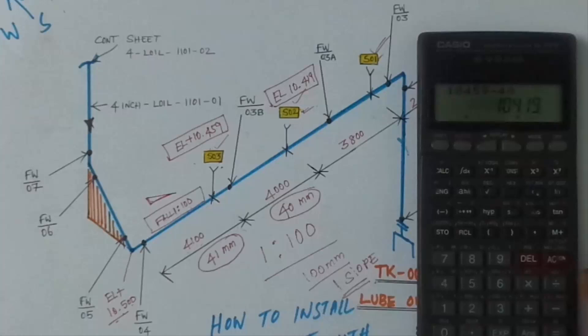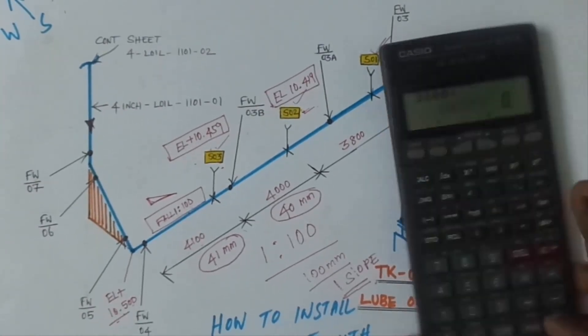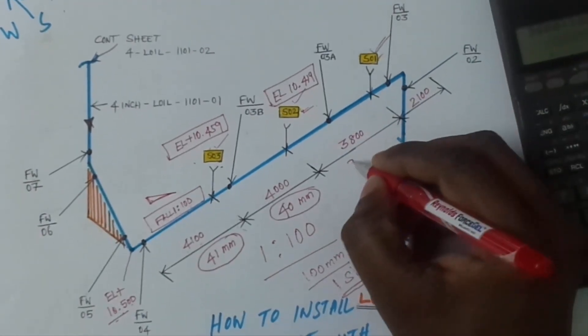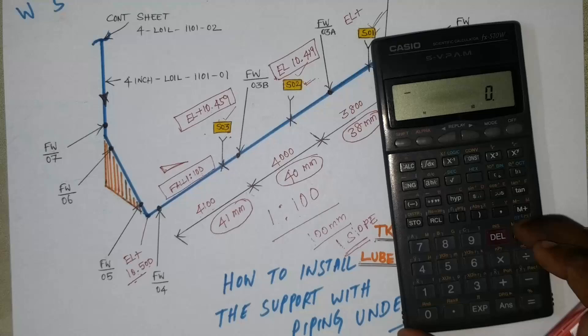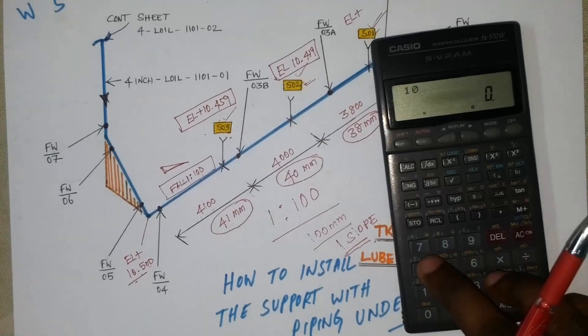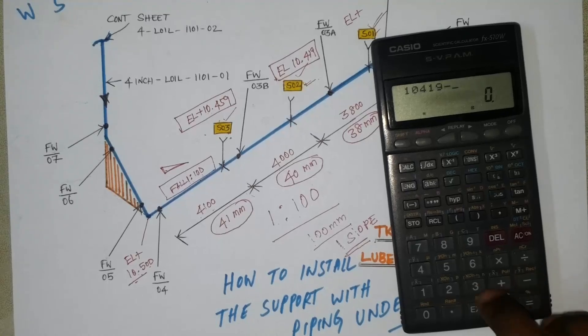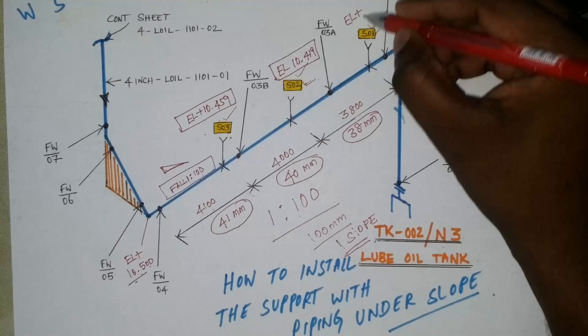So 3.8 meter, 1 is 100, so 38 mm in difference. So from last elevation 10 meter 419 minus 38 mm, so elevation is 10.381 m for support number 1.